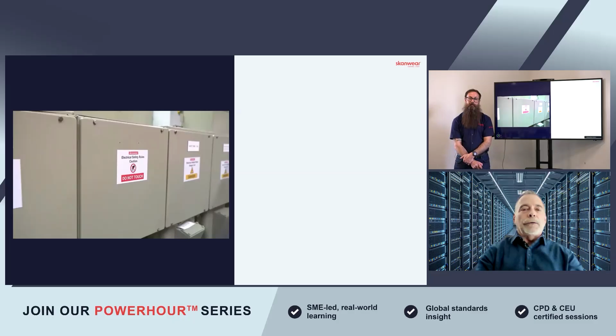Grounding clusters are important to number, as you have in the picture here, within your MOPs, because when you go back to re-energization, we have sometimes seen grounding clusters get left on equipment and cabinet doors get closed, maybe without signage like we see here, where signage is on every piece of equipment, bolted or non-bolted hinged cabinets. If those aren't there and you don't have a trackable grounding cluster, you may forget they're there due to the speed of the project. Then you re-energize the system onto the ground of those clusters, and that can obviously lead to problems. So having a good tracking process for your clusters is important.